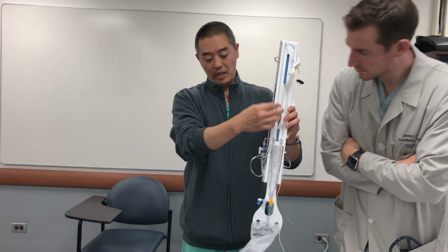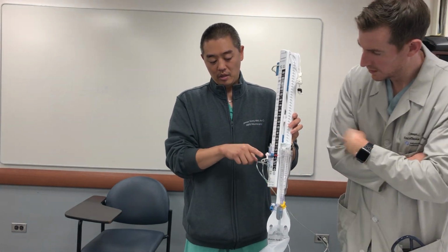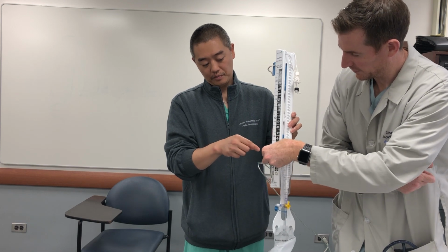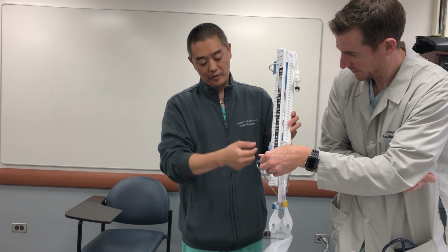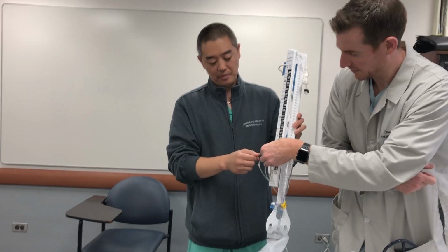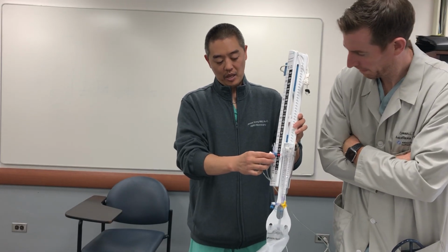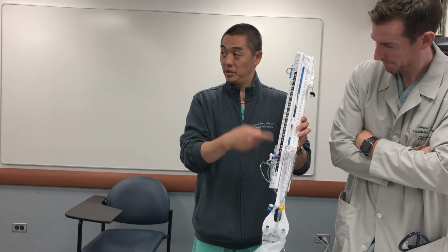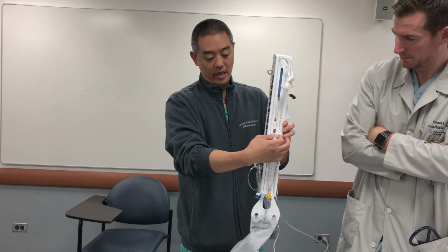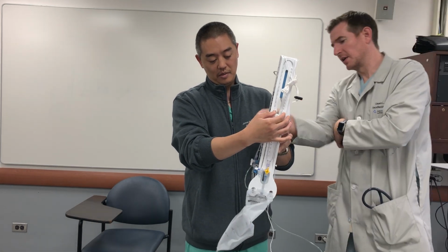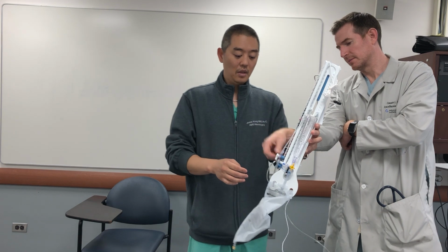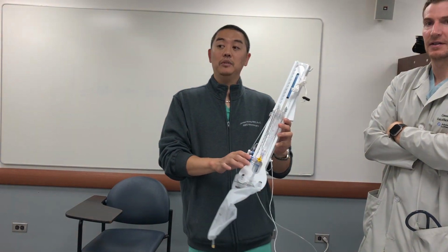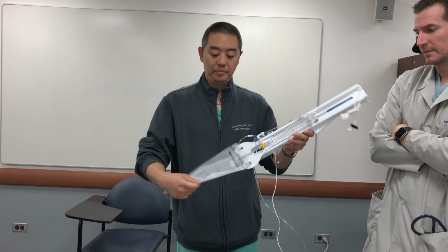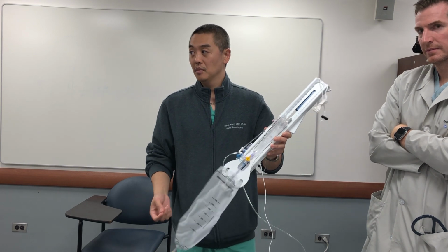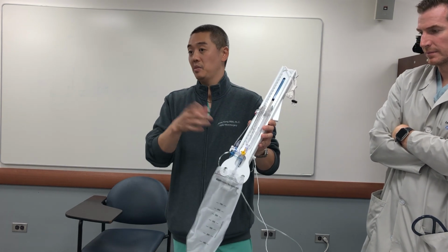So as soon as you bring it down to 0, you have the transducer. So you're going to be off to the patient? Yeah, off to the patient, and then you can zero it. Once you get your 0, you can bring it back up to 15. So you don't have to open this up? No, you really shouldn't, because when you do, you get infections. So that's why I like to do it that way, because you don't even have to take the cap off. Okay. No, the easiest way is like you said.